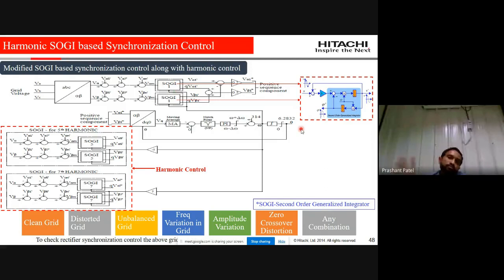In this SOGI block, we have modified some control, and we have already registered one patent for this synchronization control. We have adopted some advanced synchronization control, and after this we have not faced any problem related to synchronization. We have more than thousands of units working on sites, but we have not noticed any synchronization failure issues from the sites. The condition is not only a clean grid or only a distorted grid, but any combination of grid conditions. Suppose a grid is distorted and also unbalanced, with a frequency variation, amplitude variation, and zero crossover distortion. Even in such worst conditions, this synchronization control is working fine.